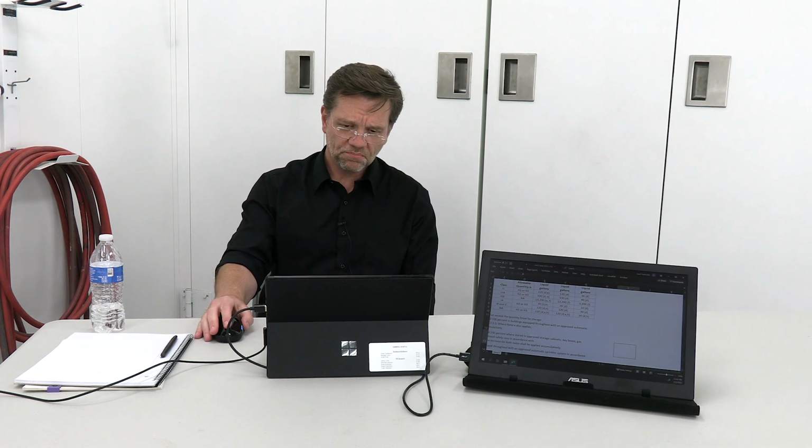So for comparison, a 16-foot by 8-foot mix room has the capacity to hold 256 gallons. An equivalently sized GFS hazardous material storage building has a maximum capacity of 550 gallons when protected by a sprinkler system and 625 gallons when protected by a dry chem system.